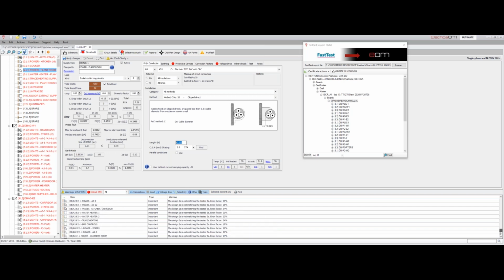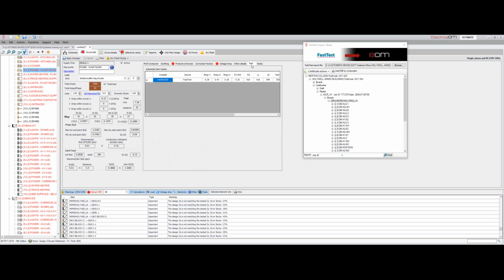We can also go all the way down to the test data, comparing the maximum test results for the ZS rating against the R1, R2 values, to see where the information doesn't match and how far out the calculated values are from what we'd expect. We're taking all this data and trying to make it meaningful, so the next time you test this installation, it will keep adding new lines to the test data, and over time you can see all that data build up.